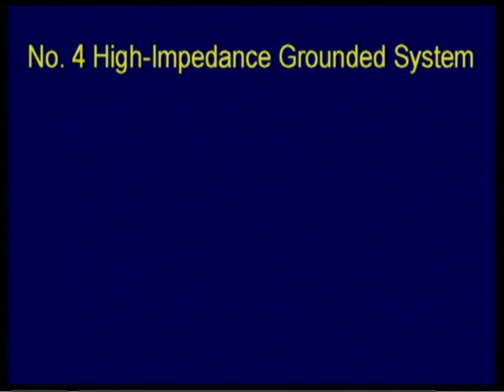See a lot of installations on these kind of systems where you have a remote location, just need a 3-phase motor, like oil rigs or well pumps or irrigation pivots, where they just run a corner grounded delta out there. They don't need a neutral. All they need is power for that 3-phase motor. Makes sense. Total sense. Corner ground one phase, and a lot of times put a 2-pole breaker or 2-pole disconnect. A lot of times it's open delta, and the power company saves money on one transformer.